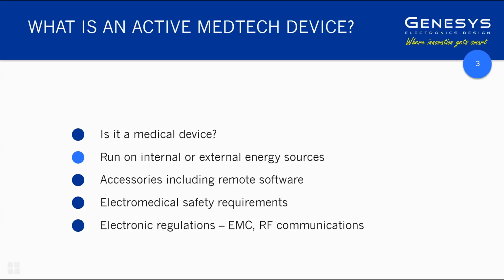But primarily, when we talk about an active device, and this really differentiates it from other medical devices which may be inert, or even pharmaceutical technologies, which are often considered medical technology, active medtech usually runs on an energy source of some sort, internal or external, meaning it's either battery powered or plugged into the mains.